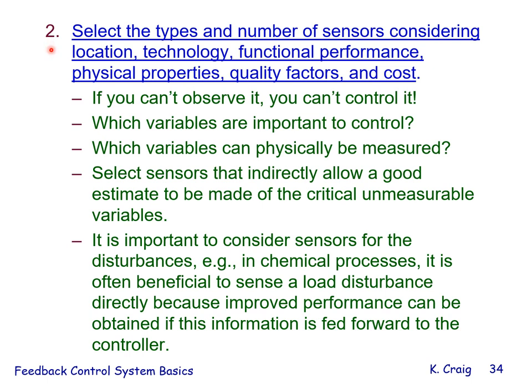Step 2: select the types and number of sensors considering location, technology, functional performance, physical properties, quality factors, and cost. If you can't observe it, you can't control it. Select sensors that allow a good estimate of critical unmeasurable variables. It is important to consider sensors for disturbances — for example, in chemical processes it is often beneficial to sense a load disturbance directly because improved performance can be obtained if this information is fed forward to the controller, which is disturbance-compensated open-loop feedforward control.